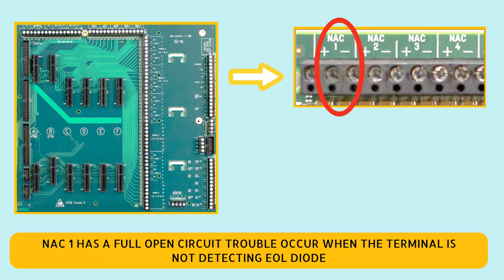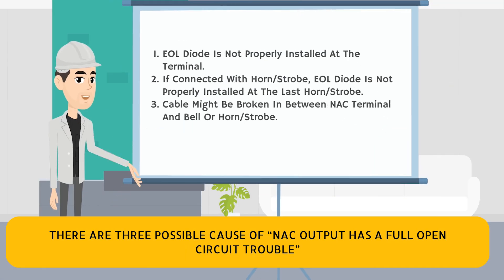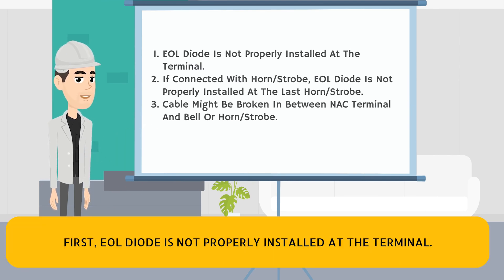There are three possible causes of NAC output full open circuit trouble. First, the EOL diode is not properly installed at the terminal.